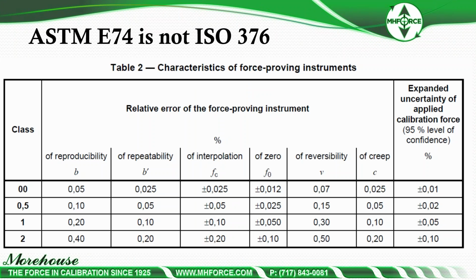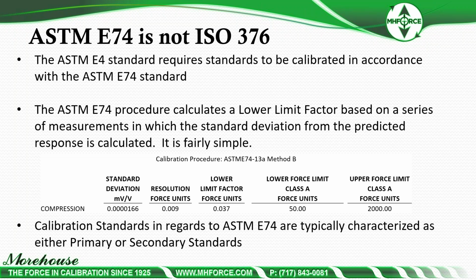There's all the characteristics again. If you look at them, these are just not in E74. Reproducibility, repeatability, interpolation, reversibility, creep, calibration standard, not there. What is in ASTM E74 is a procedure that calculates the lower limit factor based on a series of measurements in which the standard deviation from the predicted response is calculated. It's fairly simple. We're going to calculate the standard deviation.